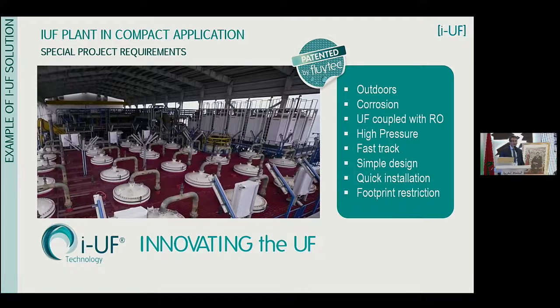Having a composite material as a pressure vessel can allow you to do a direct coupling in between the UF and the reverse osmosis high pressure pump. This means that you can save the storage tank and you can also save the pump. You can save footprint and you can save some investment on the tank. The tank is usually huge for this kind of capacities that we are talking about, and also the transfer pump can be avoided. Thus, you can save some energy as well as some money there.